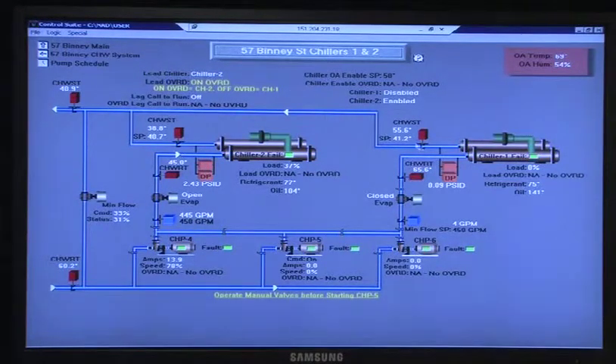If it's something you want, we can look into putting in some sort of indication that it's on. It's an automated system, we're not going to be watching this all the time. When the second chiller stage comes on, are we going to get a lag alarm up on the FAS system? You get an alarm if the other one came on because it failed. If the lag just calls to run and comes on, you won't. I can make that a point. That might be a good idea.